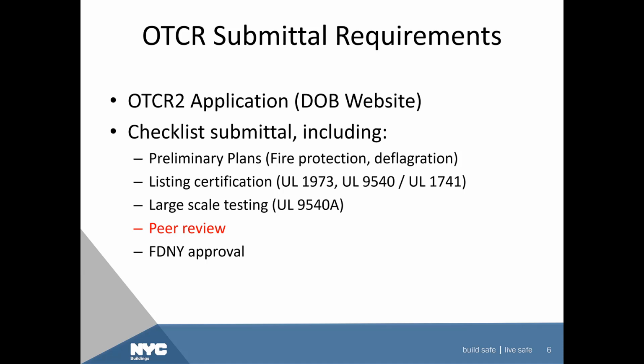The listing for an energy storage system is now covered under UL 9540. UL 9540 actually incorporates the other two standards on this slide: UL 1973 for the battery, and UL 1741 for the inverter. UL 9540 is a system listing, so it takes into account the entire system and evaluates the installation from a system level.